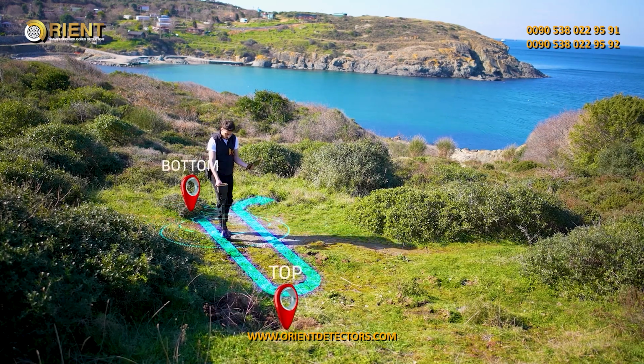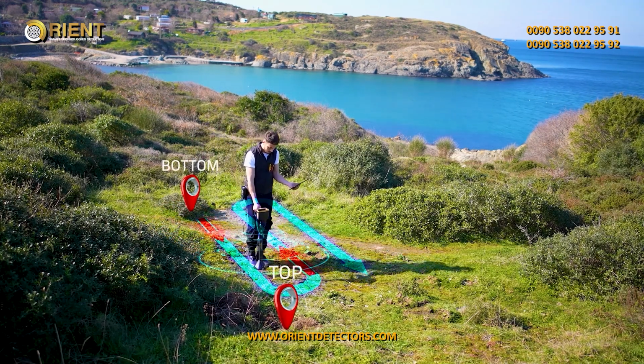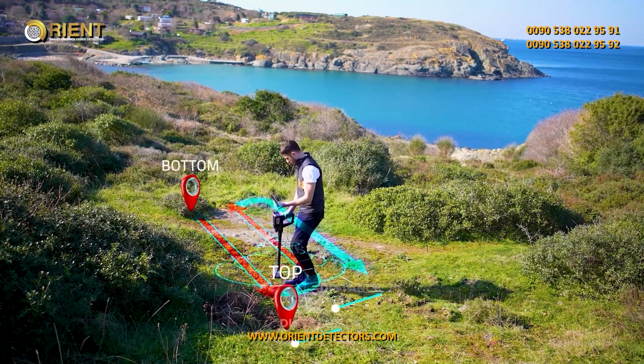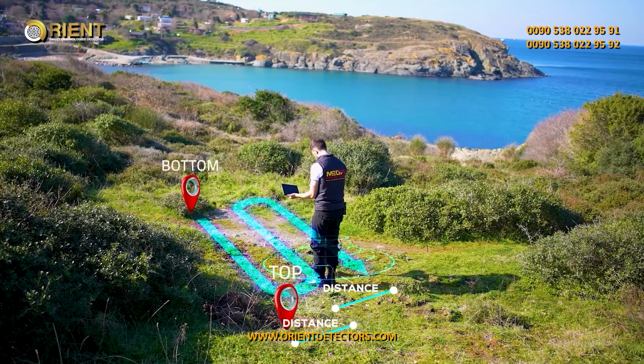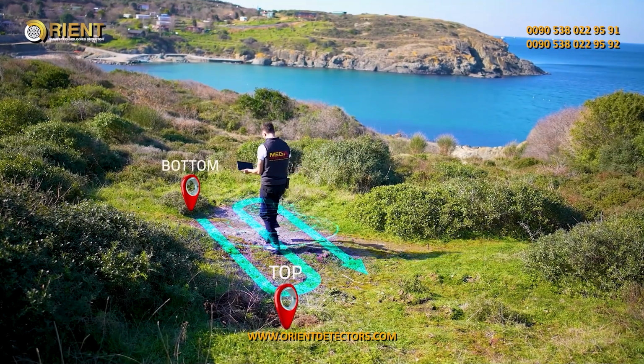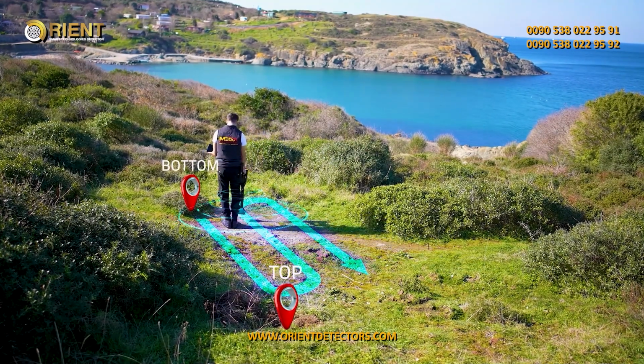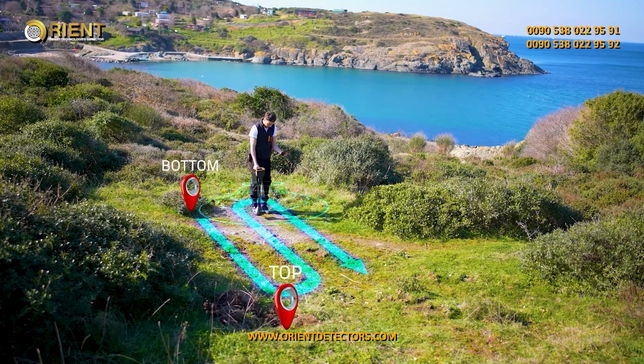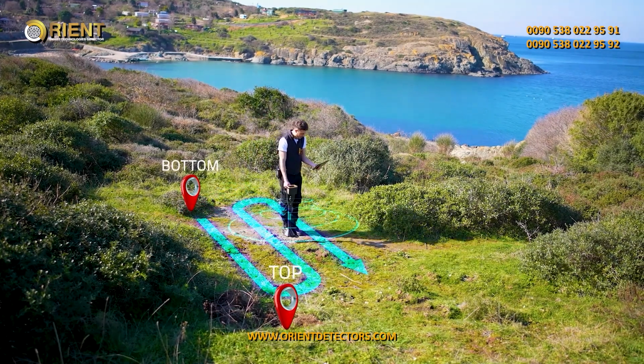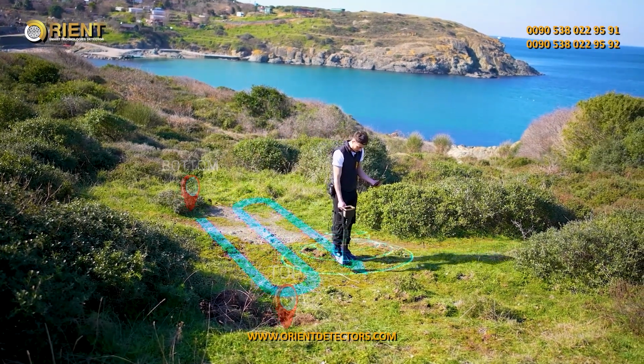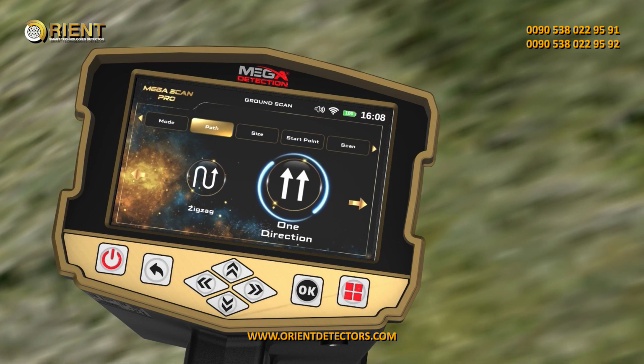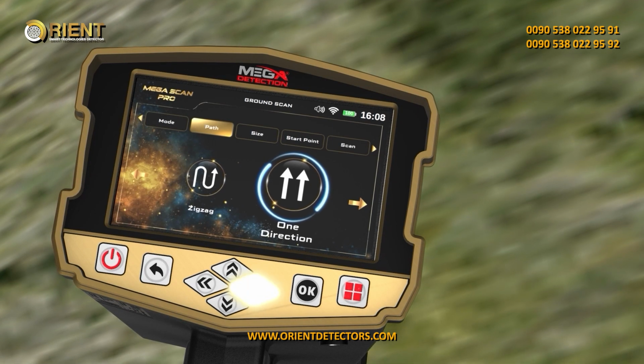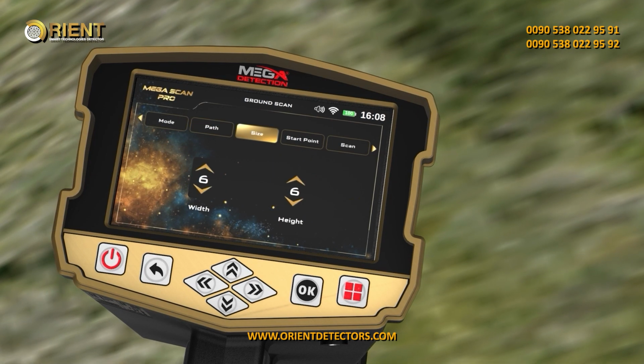In this case, the start of the next scan line is at the end of the previous scan line, while leaving an offset distance, meaning that every two successive lines are scanned in opposite directions. Select your preferred scan path mode using the left-right arrow buttons, then press the OK button.